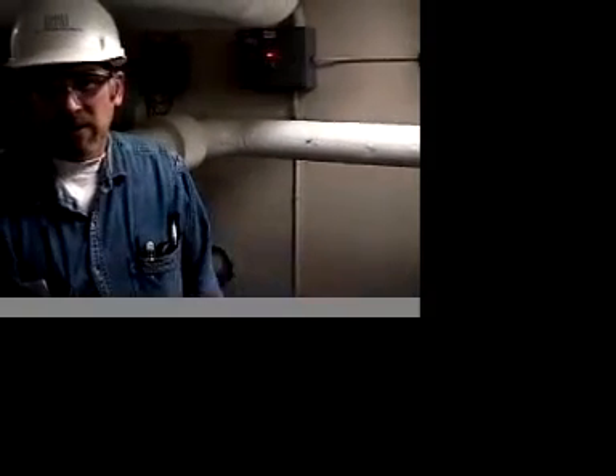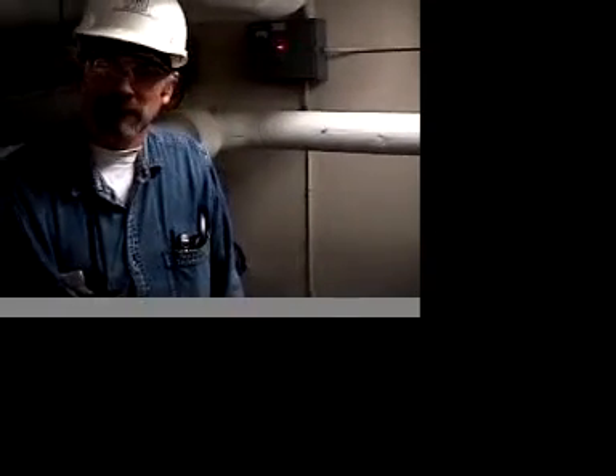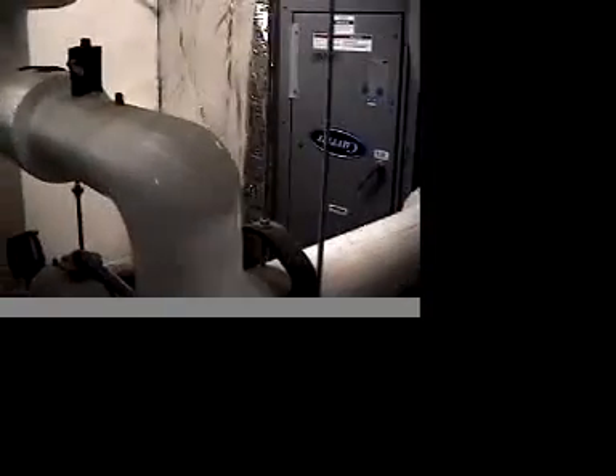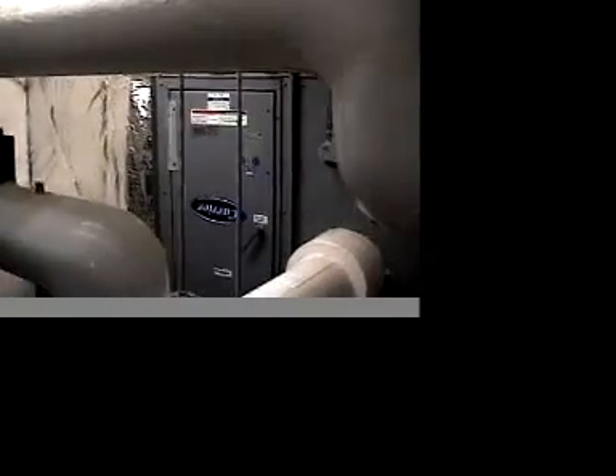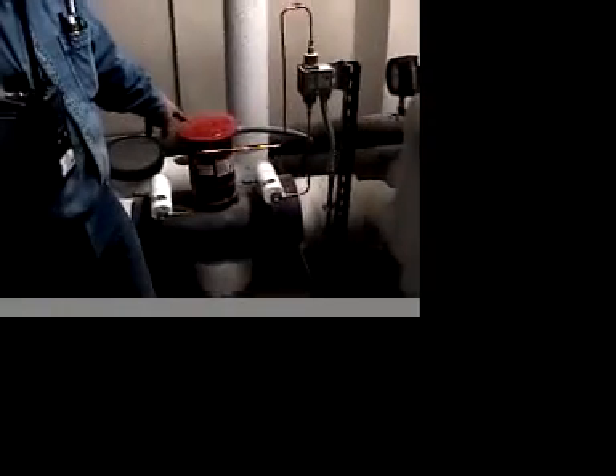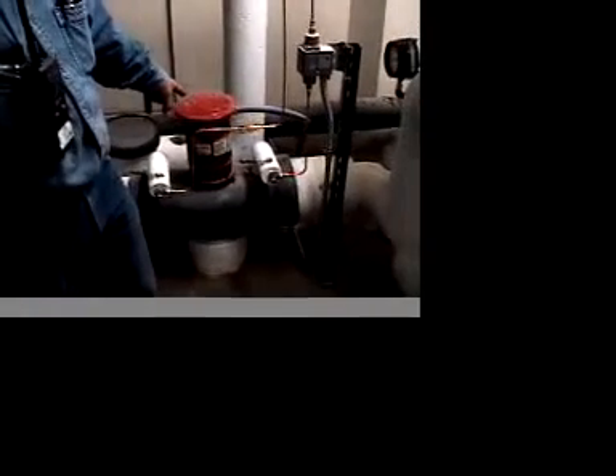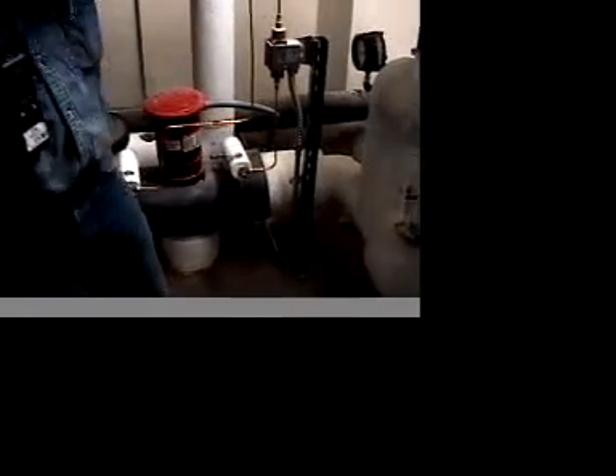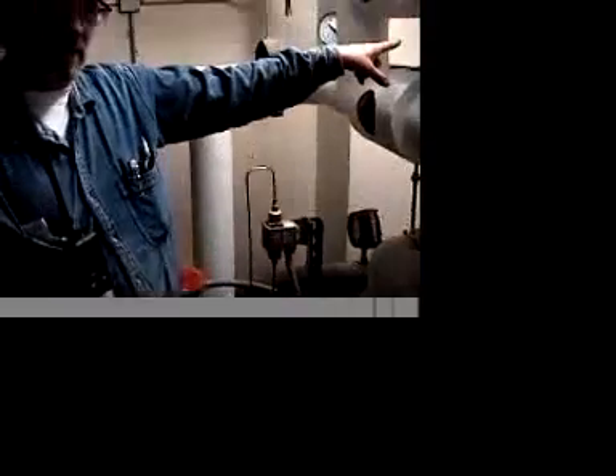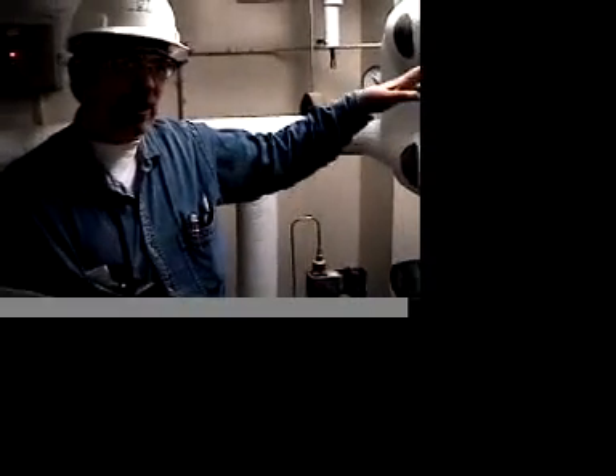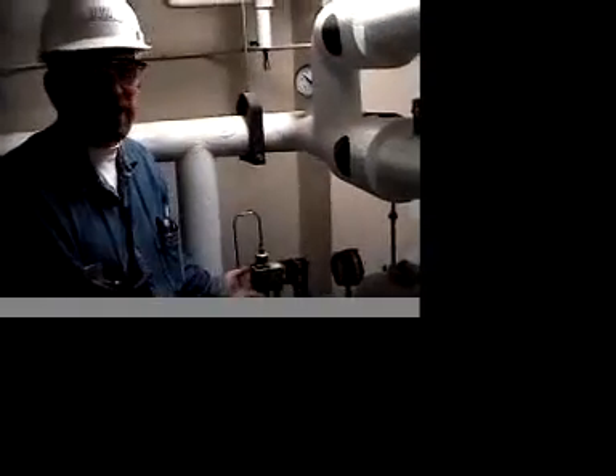Okay. Now this is a water system, not a glycol system. Correct. And this air handler here is a 100% OA air handler. Correct. So what do we do about freeze protection here? Tell us about freeze protection. The pump right here, that pump always has to be in operation. I know you have an outside air damper in there, so I guess if the pump goes down, it should be set up so that it shuts.